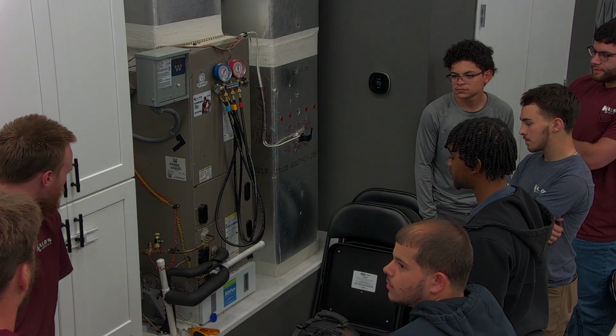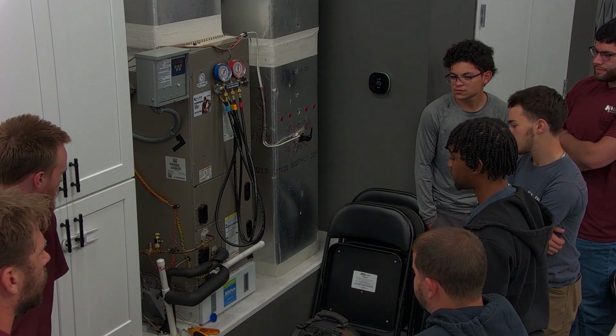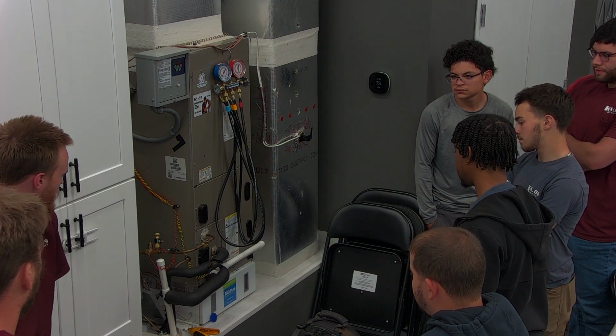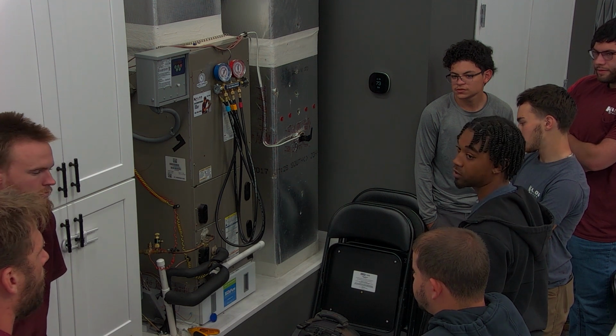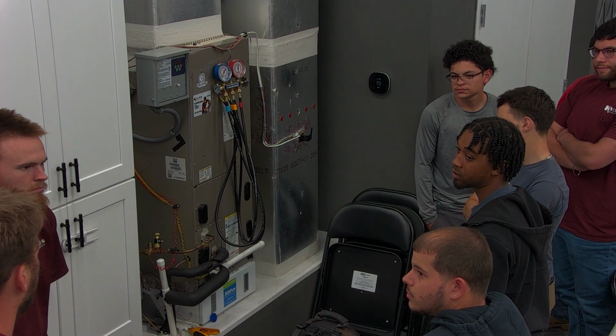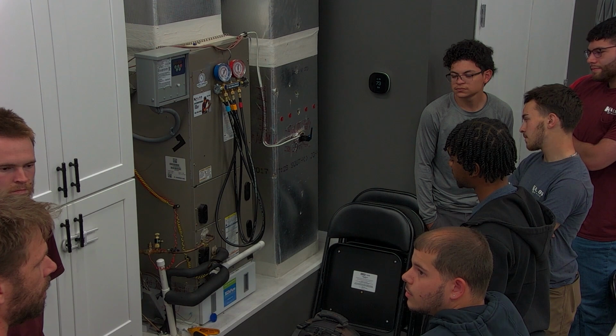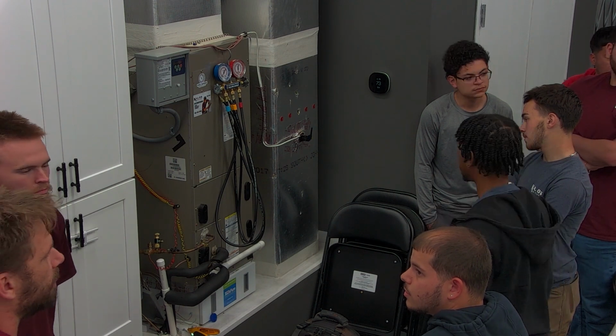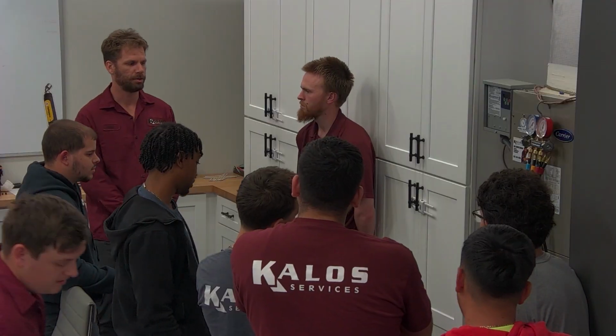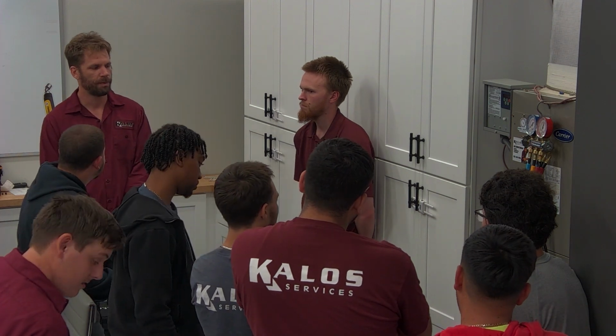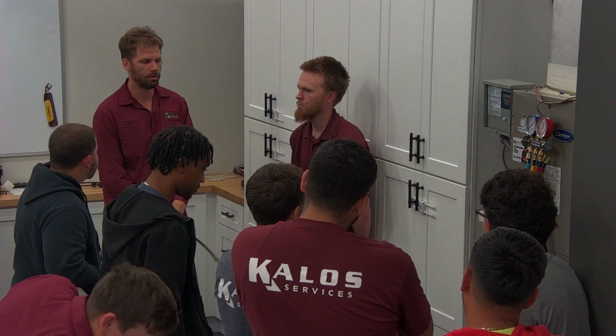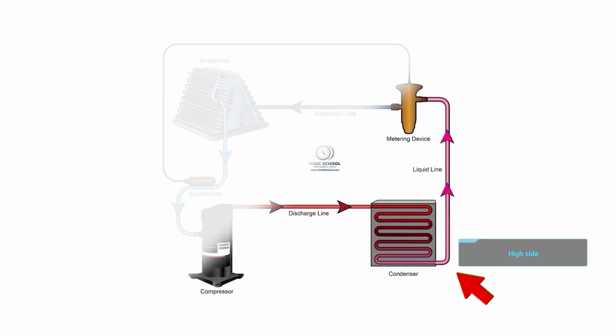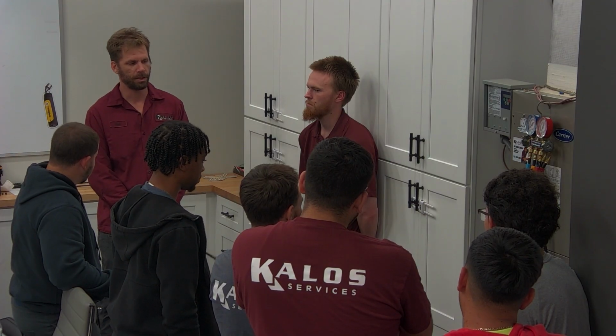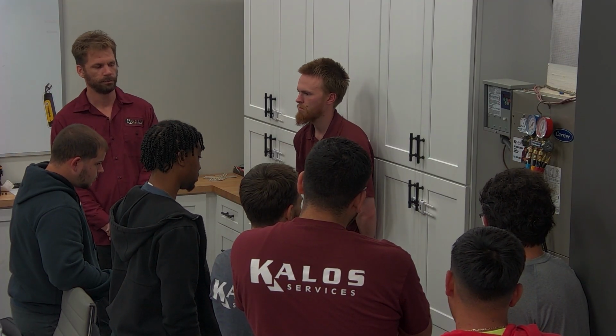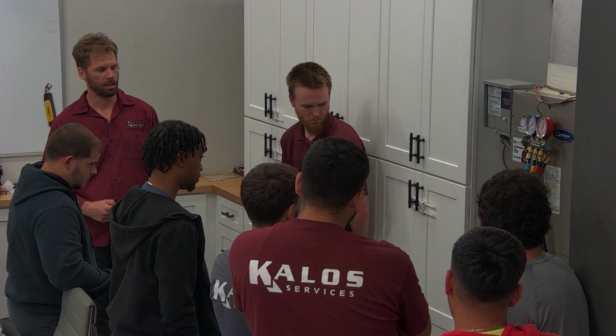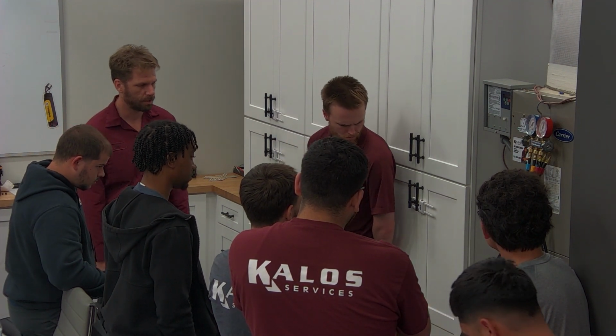Why can't we measure our superheat from right here? Because there's no access to the suction line. Well, why do we need access to the suction line? We need to know our saturation temperature. Great. Well, we do have a port to our high side. So let's go ahead, hook up, press in the Schrader, and let's get a subcool.